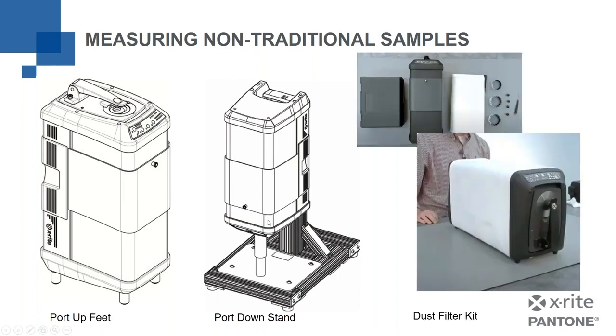And this dust filter kit, and I mention this for this reason. There are some situations where you may be in an extremely dusty environment based on what it is that you're producing. And we all know that dust and electronics don't agree with each other. Electronics are like a magnet for dust. And so the dust can get inside the device and cause issues. It can cause the lamp to start to misbehave and so forth. This filter kit and this wrap that goes around the instrument stops that contamination from happening.